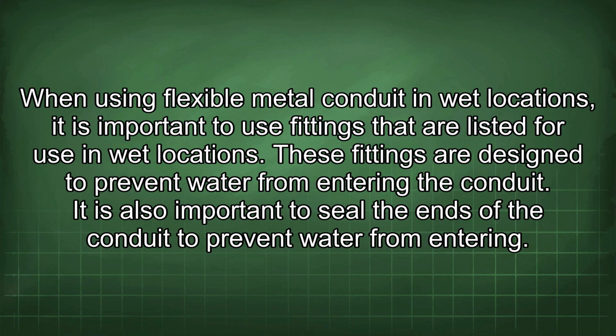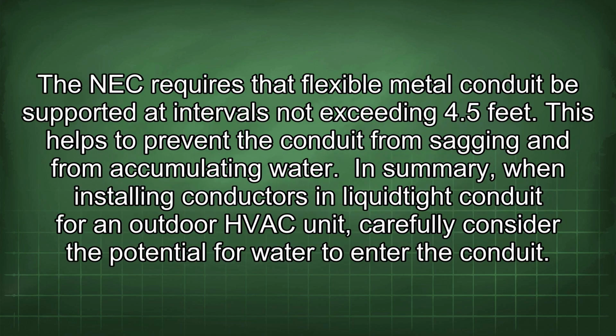It is also important to seal the ends of the conduit to prevent water from entering. The NEC requires that flexible metal conduit be supported at intervals not exceeding 4.5 feet. This helps to prevent the conduit from sagging and from accumulating water.